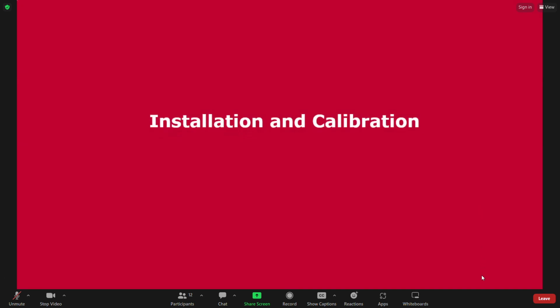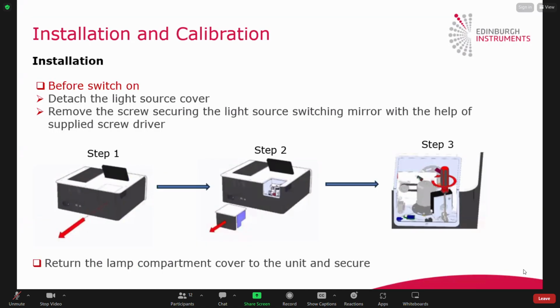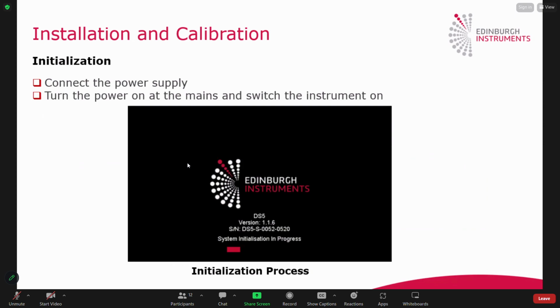Now I would like to move on to talk about the installation and calibration. So remember, before you switch on the instrument, you need to detach the light source cover here. Then you remove the screw securing the light source switching lever with the help of the supplied screwdriver. Then the light source switching lever can move freely. Then you remember to return the lamp compartment cover to the instrument and secure the light source unit. Then you can connect it to the power supply, and you turn on the power of the instrument.